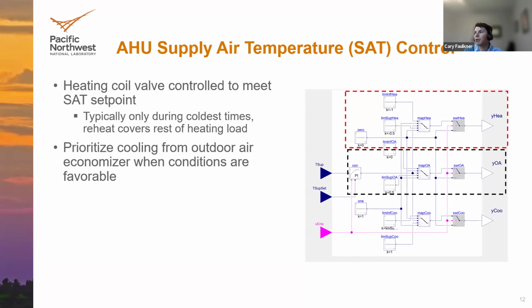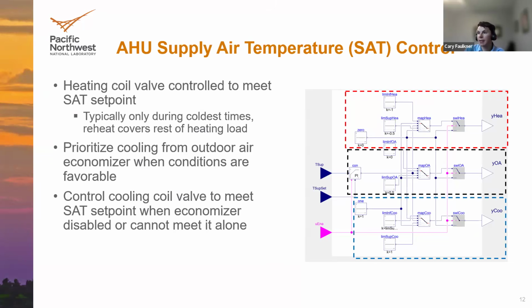And there's going to be a similar signal from that based on the supply temperature measurement and set point, and then the outdoor air temperature. And then the last aspect is going to be controlling the cooling coil valve to meet the supply temperature set point when cooling is needed, as well as when the economizer is either disabled because it's too hot or humid out, or it just can't meet the set point alone. So that's going to be that last block there.